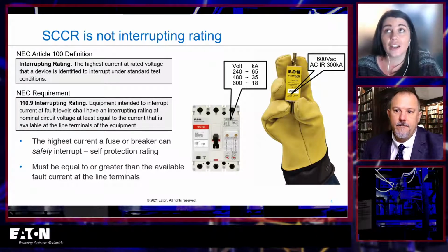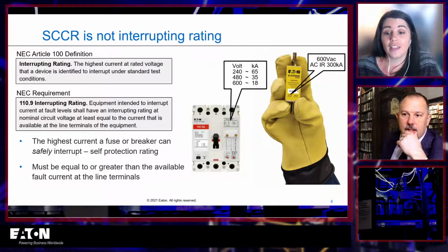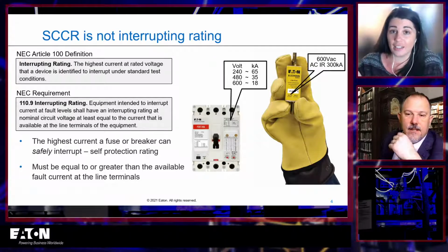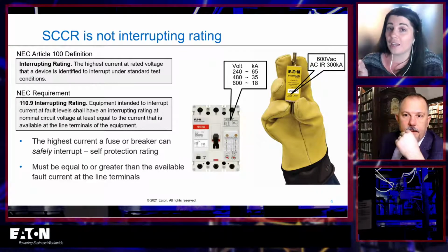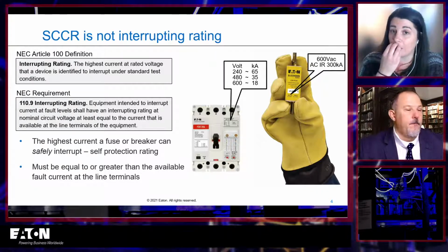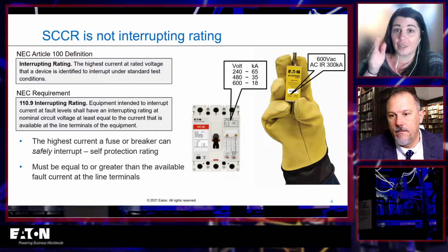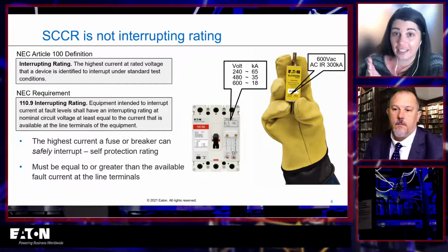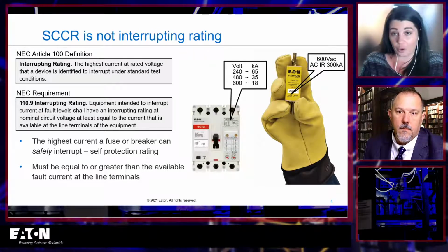Correct. When you see AIC, it should only apply to something with an interrupting rating, because the I is interrupting. And the only thing that's doing anything during it is the overcurrent protective device.